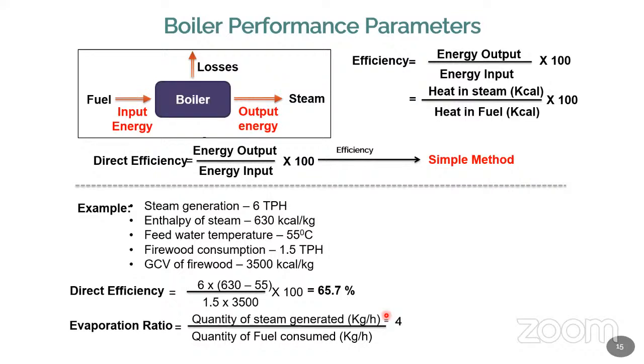So for water, you can fit a water flow meter in the feed water tank. At the water input point of the boiler, you can put a water flow meter, which is available, like the one normally available in your home. If you have corporation water at home, there is a meter which keeps on rotating when you take water, and it shows how much water you have taken. So for 1 hour, how much water you are feeding into the boiler can be measured.